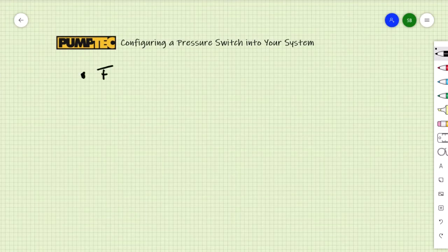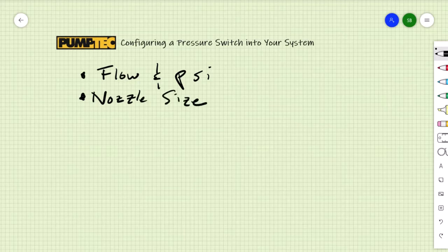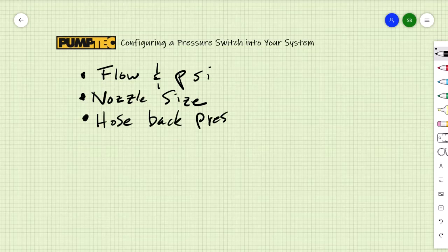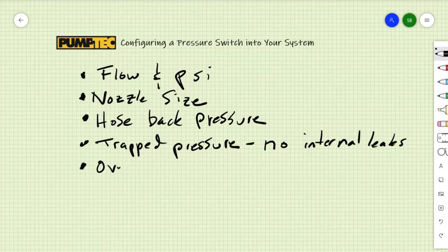Things to consider when designing a system to run correctly with a pressure switch include flow and pressure performance of the pump, nozzle size, hose back pressure, trapped pressure and no internal leaks, the use of an overpressure safety device, and fluid compatibility.